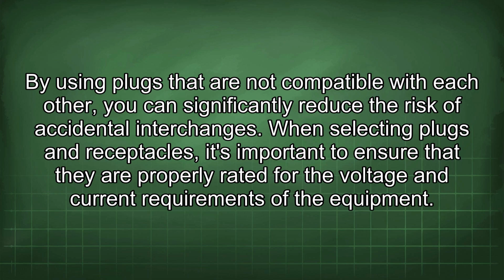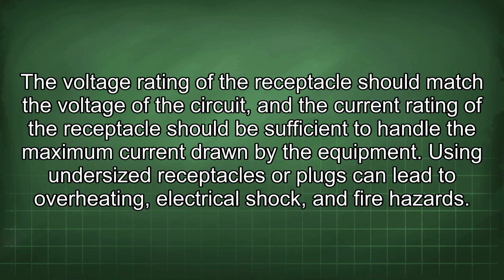When selecting plugs and receptacles, it's important to ensure that they are properly rated for the voltage and current requirements of the equipment. The voltage rating of the receptacle should match the voltage of the circuit, and the current rating of the receptacle should be sufficient to handle the maximum current drawn by the equipment. Using undersized receptacles or plugs can lead to overheating, electrical shock, and fire hazards.